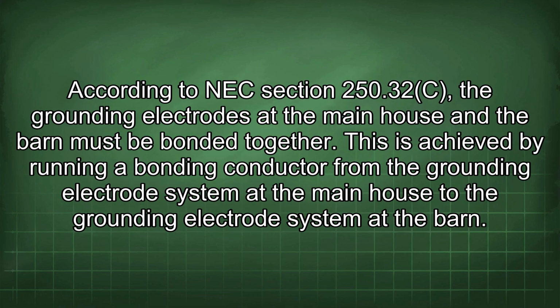According to NEC Section 250.32(C), the grounding electrodes at the main house and the barn must be bonded together. This is achieved by running a bonding conductor from the grounding electrode system at the main house to the grounding electrode system at the barn.